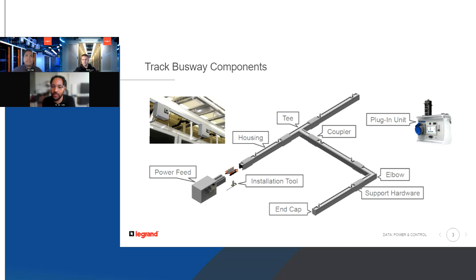There's no downside. They both pass UL 857, so they're both rated the same, both the copper solution and the hybrid solution, for example rated for a 1,000 amp bus. The benefit of the copper aluminum system is that the short circuit rating is a little bit higher than the copper solution, because there's inherently a bit more resistance with the hybrid solution, so you get a better short circuit in that manner. But both systems pass UL 857 and give that same level of confidence that you can push it all the way up to whatever current rating the busway is rated for.